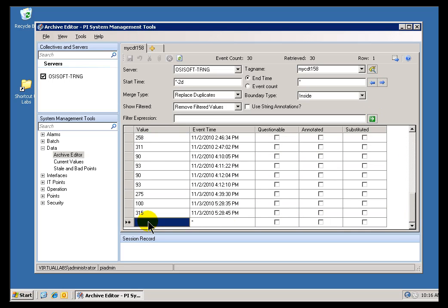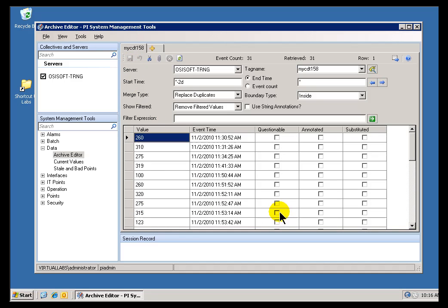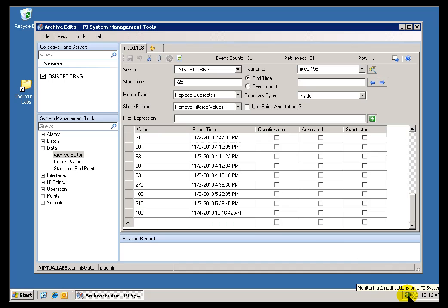This is the one where it goes above, if it goes above, what was it, 250, I believe we have an Alarm. When it goes above 300, we have a more severe Alarm. So, I'm going to go ahead and take it out of Alarm State. So, this should reflect that we no longer have anything in an Alarm State at this point. It's still monitoring these Tags. There we go.